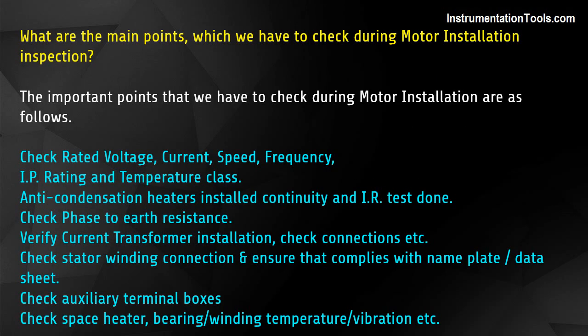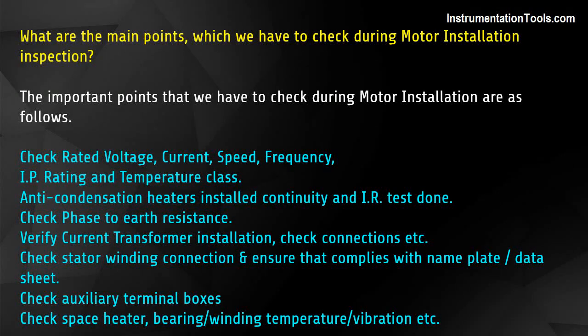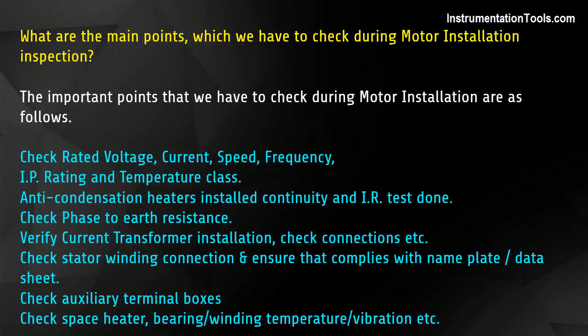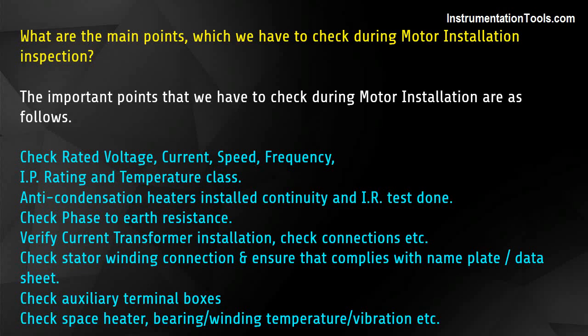What are the main points to check during motor installation inspection? Check rated voltage, current, speed, frequency, IP rating, and temperature class. Anti-condensation heaters installed, continuity and IR test done. Check phase-to-earth resistance. Verify current transformer installation and check connections.